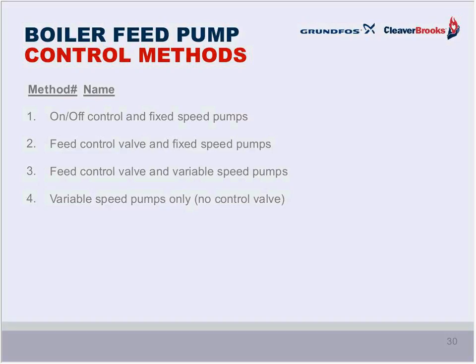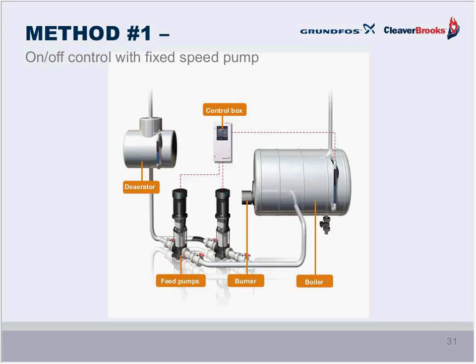Steve, I think that presentation sets up very well what I'm about to show you relative to the controls for the feed pumps themselves. We have 4 different control methods that we encounter in these systems. There's simple on-off control with a fixed speed pump, and that's the old way of doing it, still done today. Feed control valve, which Steve mentioned, and a fixed speed pump. Then we can get a little bit more advanced and go with the feed control valve with a variable speed pump. And finally, the latest way to do this was with a variable speed pump only and with no control valve. And we'll show you what the relative advantages and disadvantages of each of these are, so you can use that information to help you make decisions for the system you're working on.